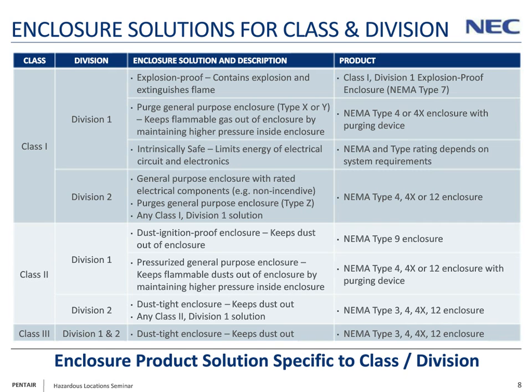You can purge and pressurize a general purpose enclosure, which means you can use general purpose electrical equipment in a NEMA Type 4 or 4X enclosure by using a purge device and system to put inert or compressed air into the enclosure to keep hazardous gas outside of the enclosure and outside the control panel. Another alternative is intrinsically safe. This is low power equipment, limits the amount of energy in the electrical circuit, and typically you would use a NEMA Type 4, 4X, or 12 enclosure with that type of equipment in a Class 1 Division 1 area.